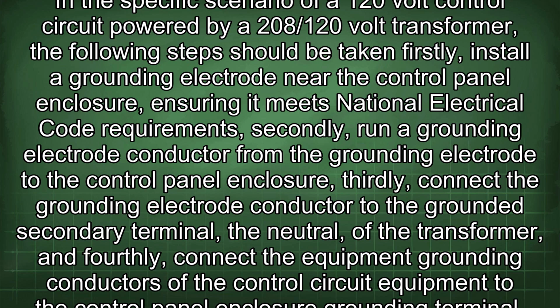In the specific scenario of a 120-volt control circuit powered by a 208/120-volt transformer, the following steps should be taken. Firstly, install a grounding electrode near the control panel enclosure, ensuring it meets National Electrical Code requirements. Secondly, run a grounding electrode conductor from the grounding electrode to the control panel enclosure. Thirdly, connect the grounding electrode conductor to the grounded secondary terminal, the neutral of the transformer.